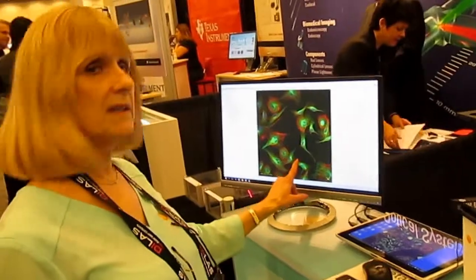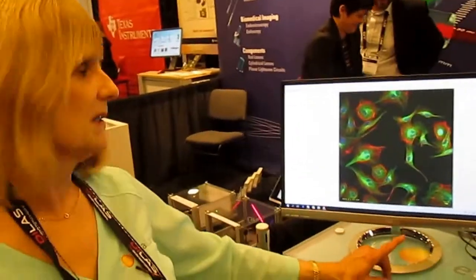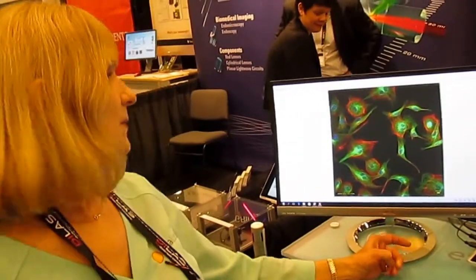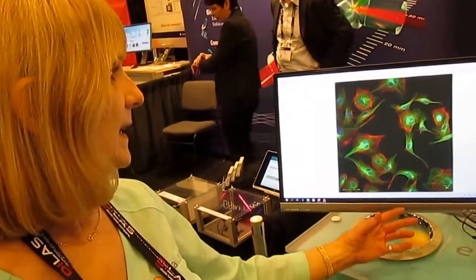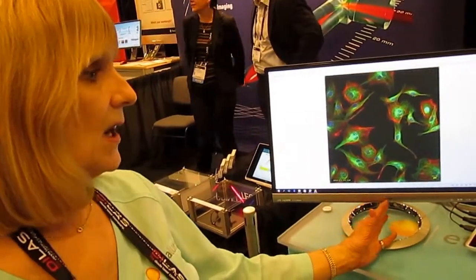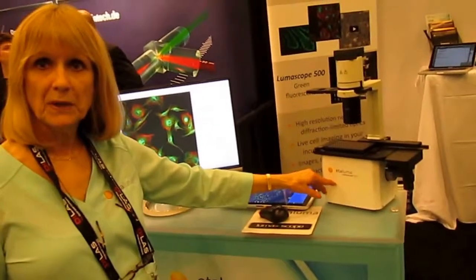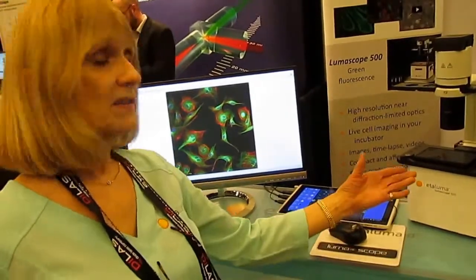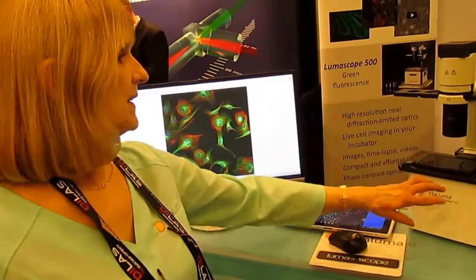So what we're showing here is a typical 3-color fluorescent image, the red, blue, and green, and again, high resolution that you can see there. Our microscopes are also very compact, so this goes into an incubator or into a hood very readily. It's a big advantage for us because they go in and out of incubators just fine for live cell imaging. They're very versatile. You can use just about any labware. This particular one connects to the computer, and it's powered and controlled by the computer only, so you don't need a separate power cord. So you can use this out in the field or other places where maybe you don't have an electrical power cord.